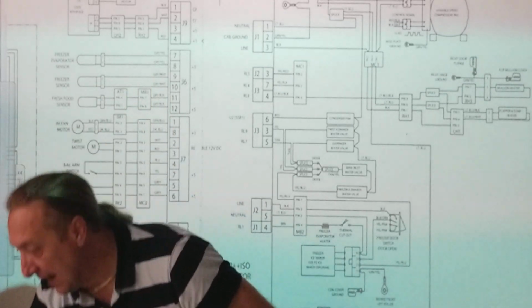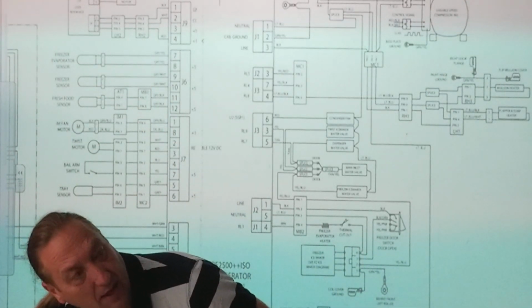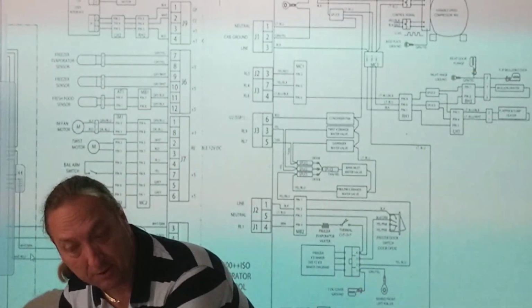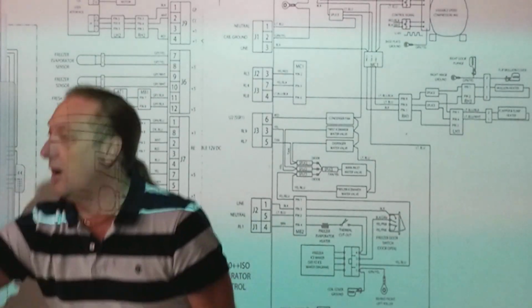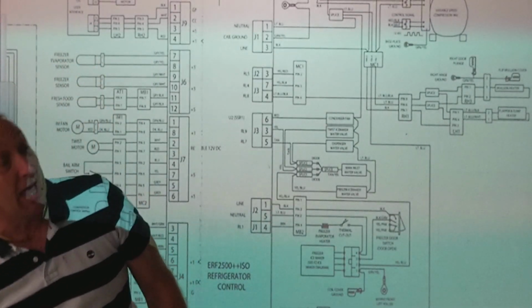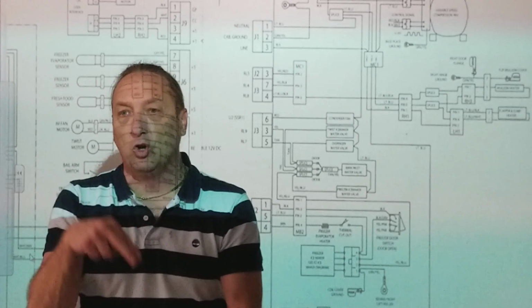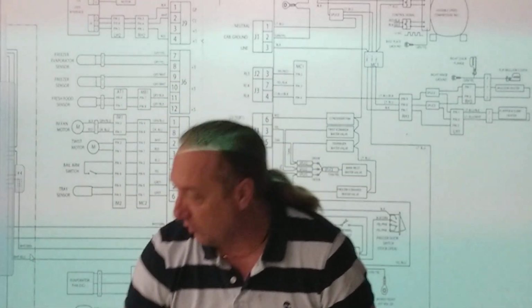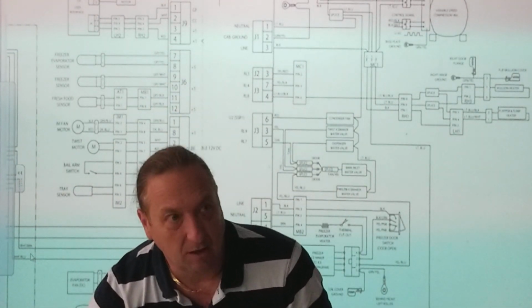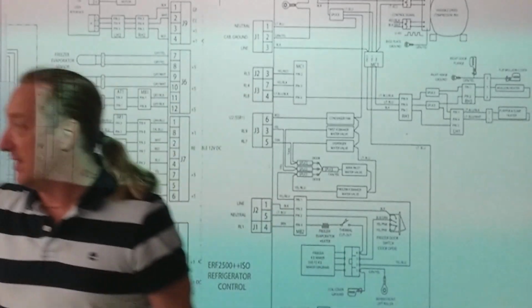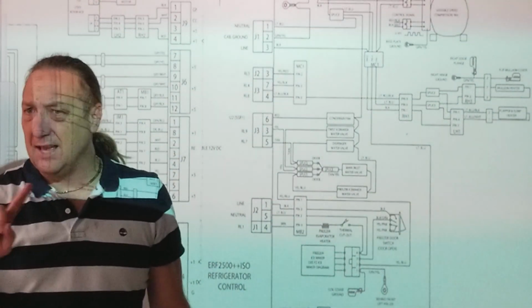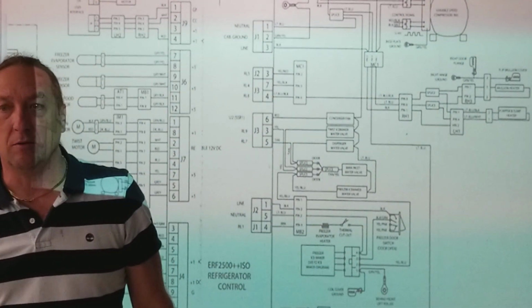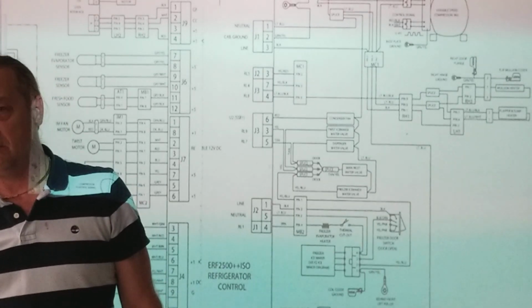So now I'm gonna go down to the board, pull the wires off the board, and touch the wires that go from here up to that sensor, and say, am I getting a good reading? Because if I get a good resistance reading from down there, but my board still says that sensor's open, the sensor's not open - what's wrong? The board. The board's bad.